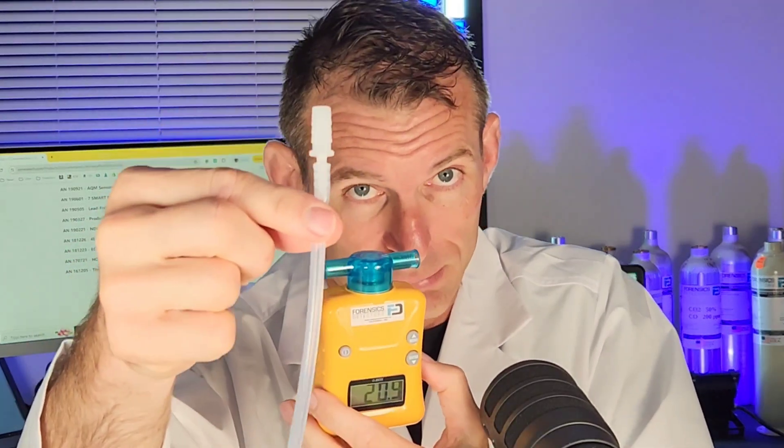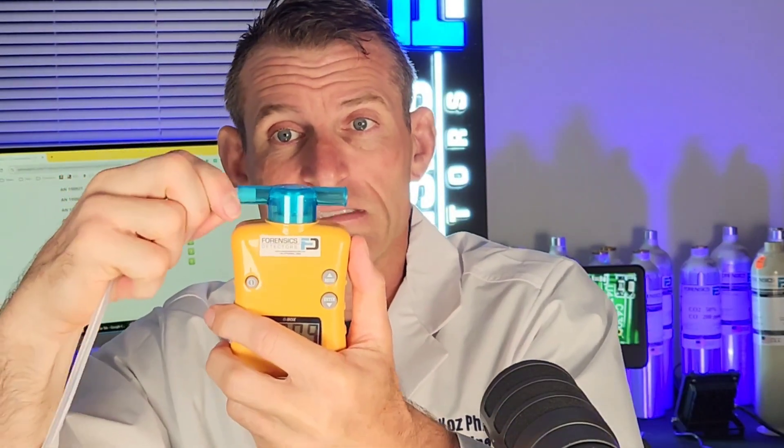Furthermore, this is very versatile. You can use it to test different oxygen sources coming from an oxygen machine, oxygen tank, or concentrator. It also comes with a coupler that fits onto the T-piece very snugly, and then you have tubing that you could pop in various places to undertake your testing. The air comes in, the sensor senses it in the T-piece, then it flows out — giving you an inline sampling system of oxygen.